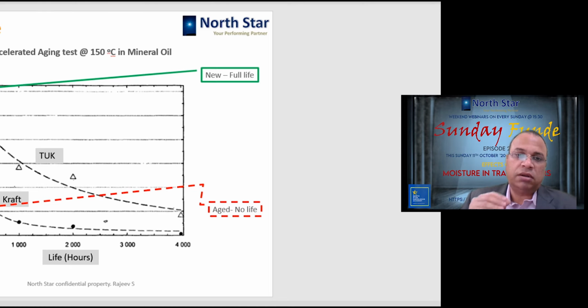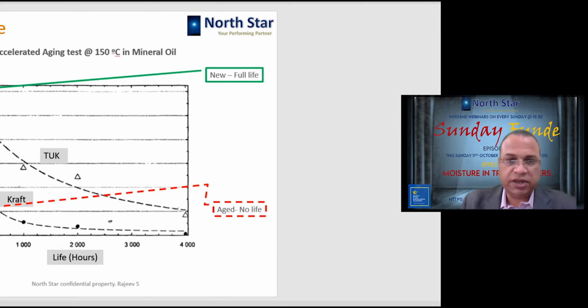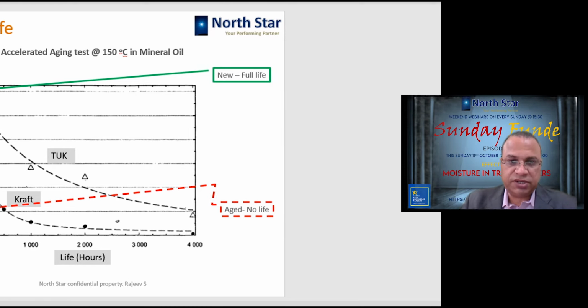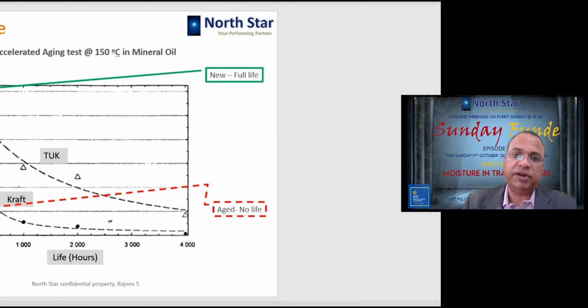So these are the materials which are now quite commonly used in sensitive and critical applications where the insulation stress is more or the effect of other parameters is going to be more on the transformer. So when you have this TUK, the graph is a little less steep compared to when you have kraft paper. It is very steep. So what we are showing here, on the y-axis it is the degree of polymerization, and on the x-axis it is the life of the insulation.